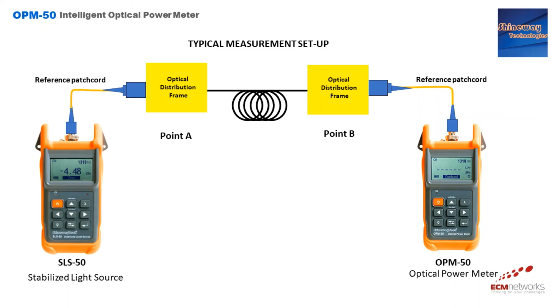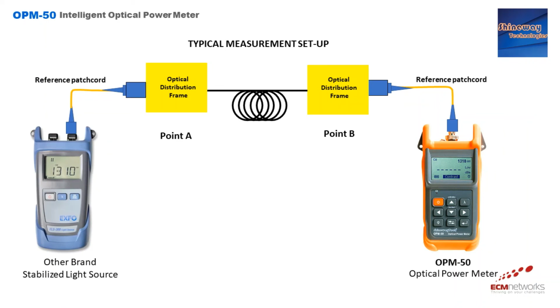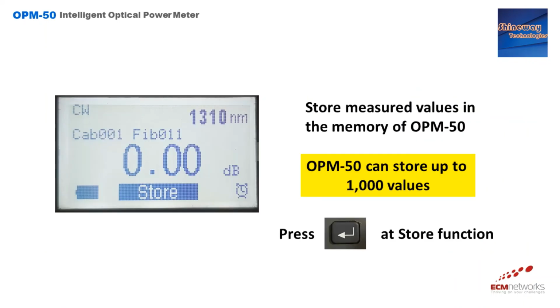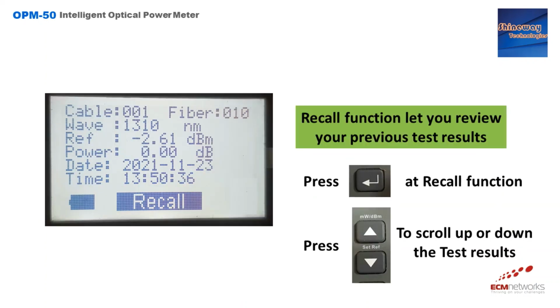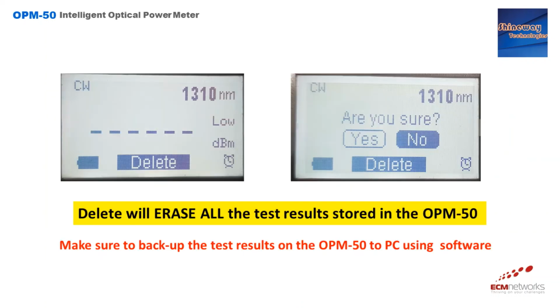This is the typical setup for optical link testing. After every test, use the store function to save the test result in the equipment. The recall function is used if you want to review the test results you have made. If you want to erase the files stored in OPM50, use the delete function. But before doing that, please back up all the test results on your PC via the OPM data analysis software using the USB cable.